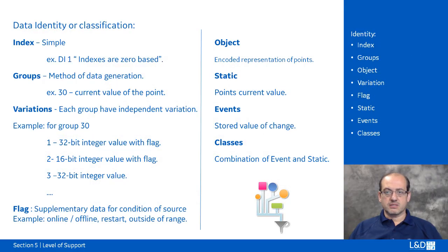One of the key things in communication in DNP is how we refer to the data that's being generated: a voltage measurement, a current measurement, a status of a breaker. All of this information that is available in our substations is basically translated into digital data, either a digital input or a digital output, an analog input or an analog output, a counter, or a status of a device.